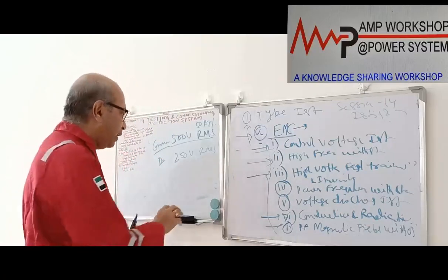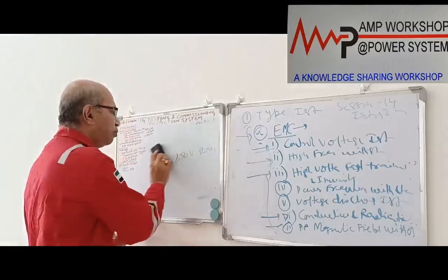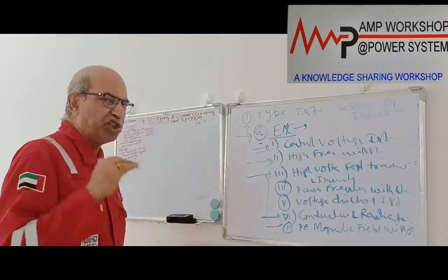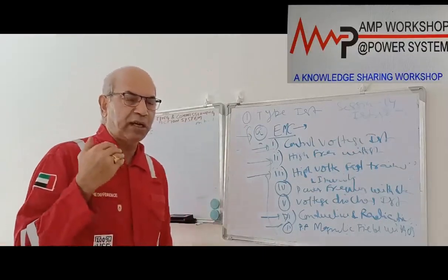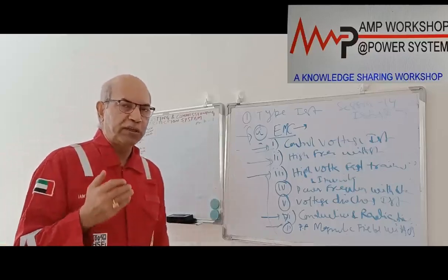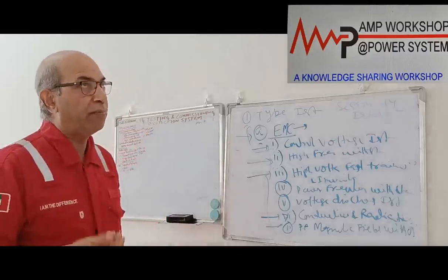That assures that the power frequency withstand voltage is there. Okay. Then the next test we carry out is the partial voltage discharge test. This discharge test assures that if there is any discharge inside the relay panel or near the relay, and due to the discharge some high voltage is generated, the relay will not operate under that high voltage.